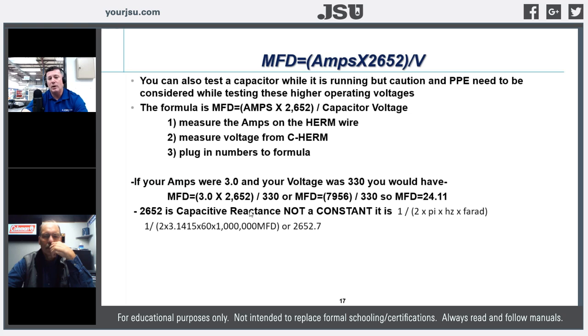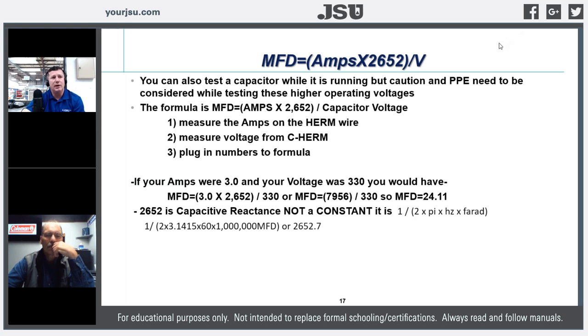So that would be approximately a 25+5 capacitor — we can calculate functional capacity under load. One thing we always have to discuss with live circuitry: PPE is completely in play here because we're talking about high potential voltage — not 240 volts, we're talking 330 plus, potentially 440 volts. A capacitor rated to 440 volts is rated to operate up into that voltage range. We did this frequently in the field to verify capacitor capability under load.